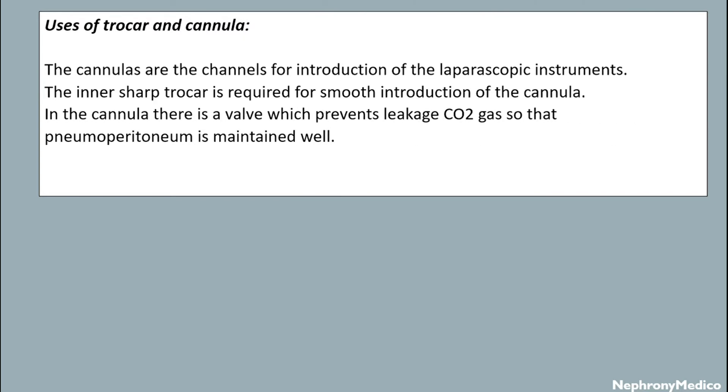Functions of trocar and cannula: the cannulas are the channel for introduction of the laparoscopic instruments. The inner sharp trocar is required for smooth introduction of the cannula. In the cannula there is a valve which prevents leakage of carbon dioxide gas so that pneumoperitoneum is maintained well.